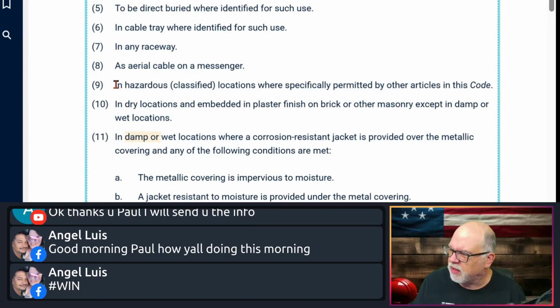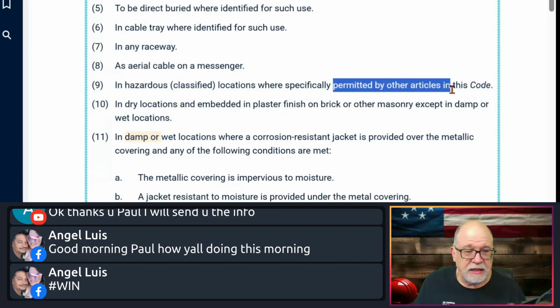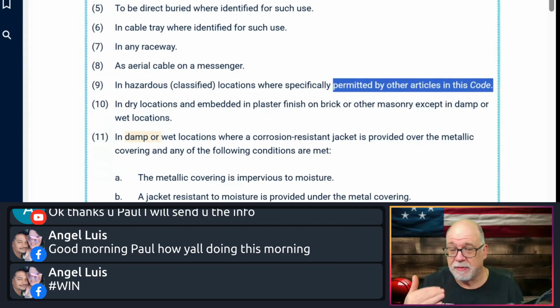In hazardous classified locations where specifically permitted by other articles in the code. So, can I use MC cable? Yes. In a hazardous location, yeah, with limited application. Depends on the class and division. But you have 500, 501, 502, 503, for example, that deals in hazardous classified locations.